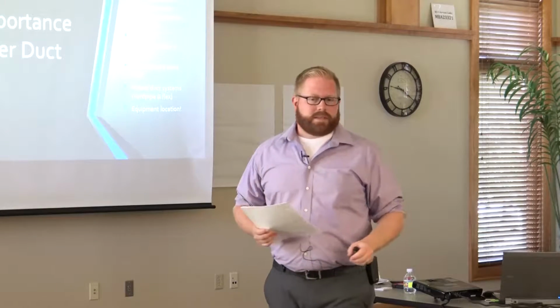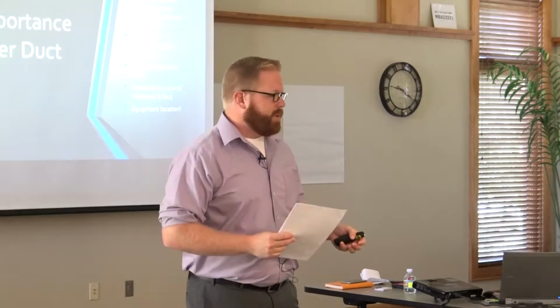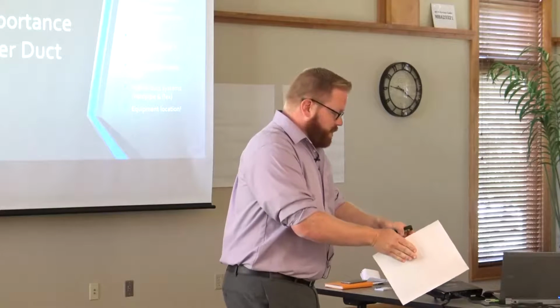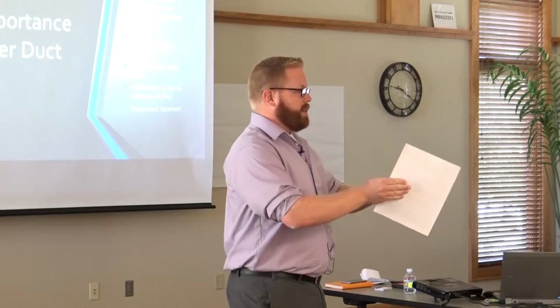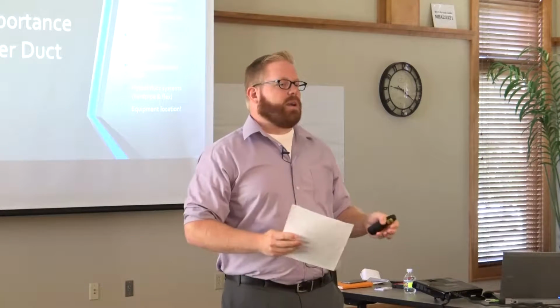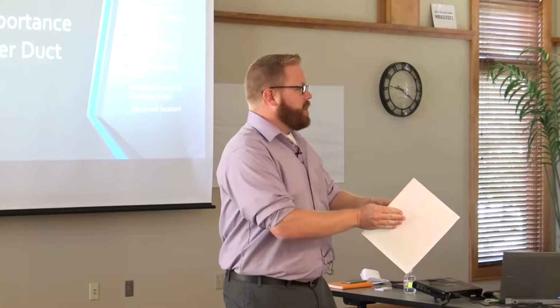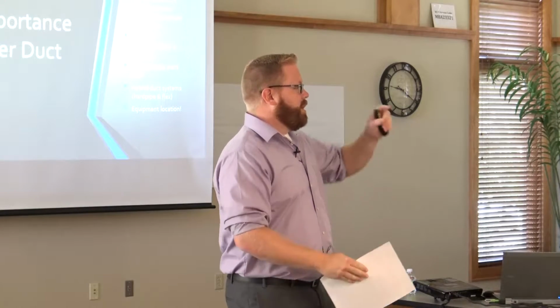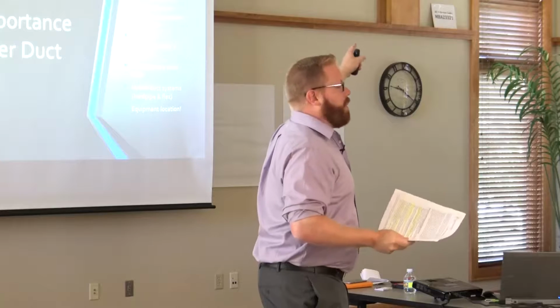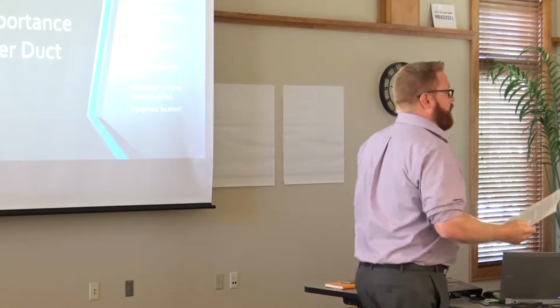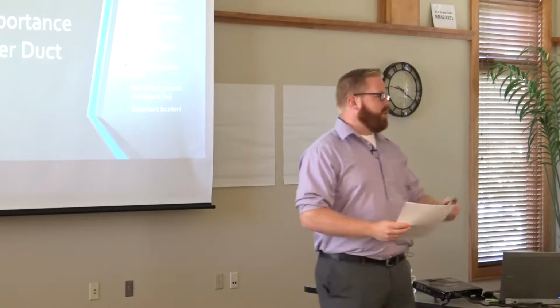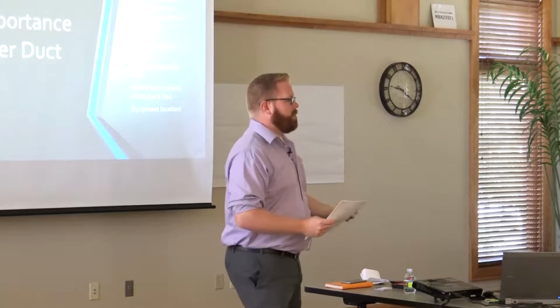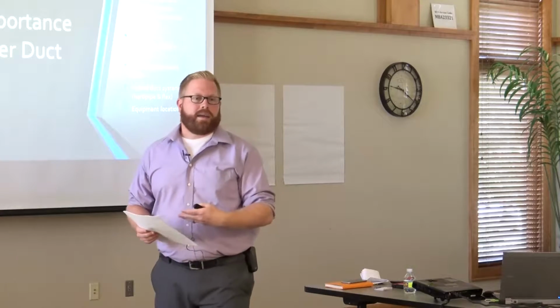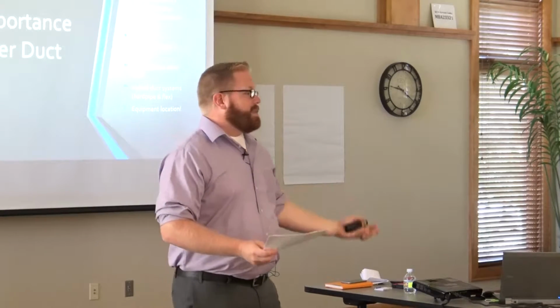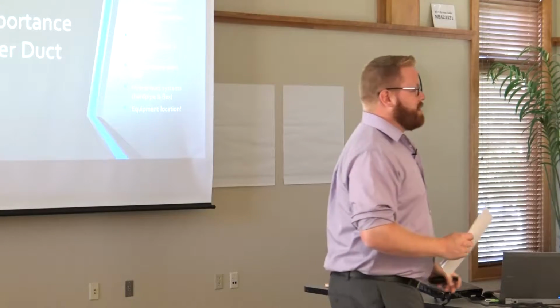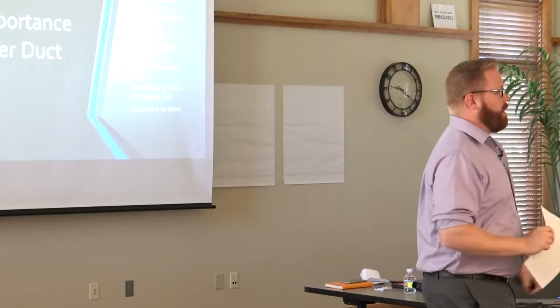But what happens is typically flex is used to be able to chase up, say between that 2x4 wall, you're trying to chase up a 6-inch heat run up between a 2x4 wall, and you're crunching that flexible ductwork to try to get it up to that second floor. So obviously we're crunching that, we're reducing the amount of airflow, the amount of CFM that that particular heat run can provide, but still passing inspection because it's installed properly.